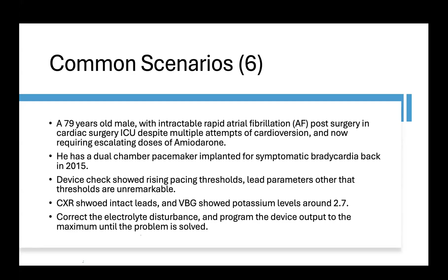device, and the device is showing rising pacing thresholds. Other than this, the device was sensing very well and the impedances were fine. The X-ray showed intact leads, and the EKG was done. It shows significantly low potassium levels. So always keep in mind to check and correct electrolyte disturbances, and in the meantime, you can program the device output to the maximum until the problem is solved.